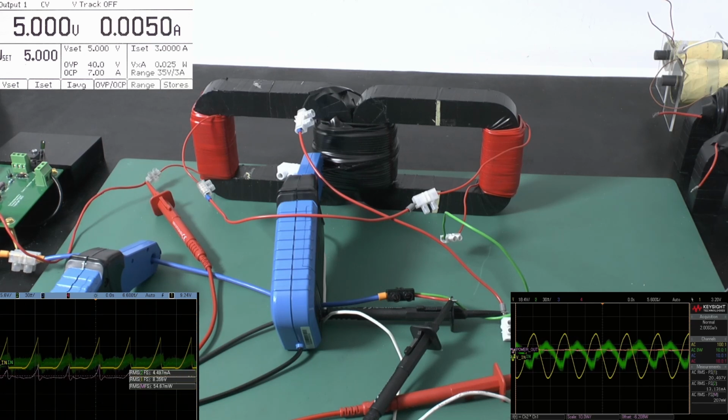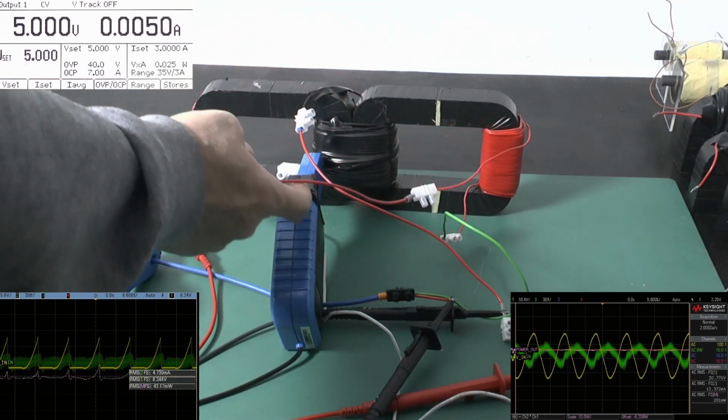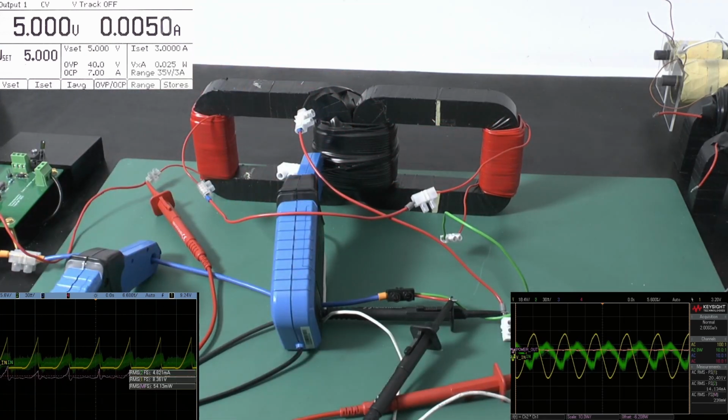That's actually showing exactly how it is. On the left hand side the green curve shows 5 milliampere, and that's exactly how much we are putting into the system from the DC power supply as well. There's not much more to say here, because in order to have more performance we need to change the wiring on the transformer. We have to cross that wire, and that will have an impact right away. So I will go over now to the next configuration with a crossover connection.